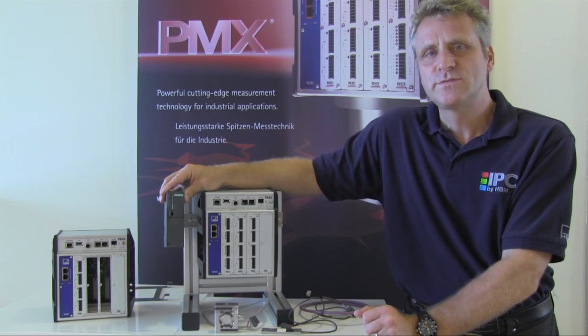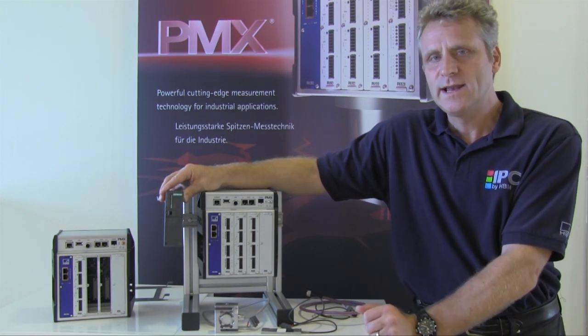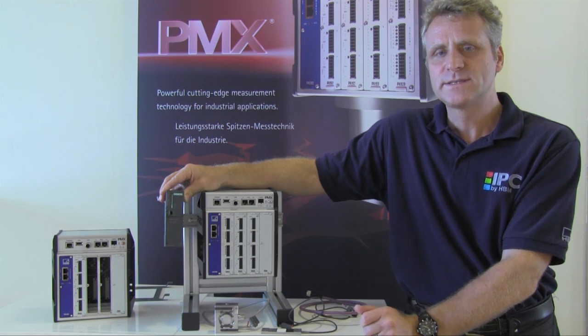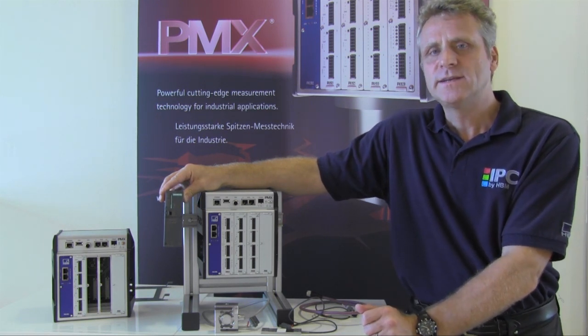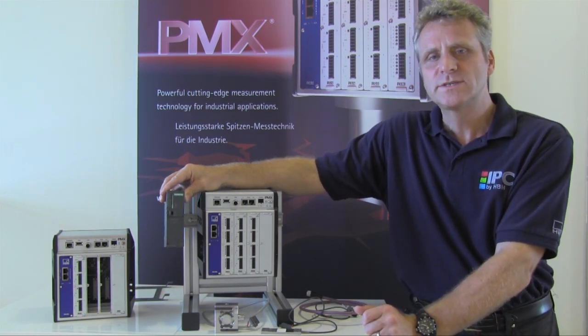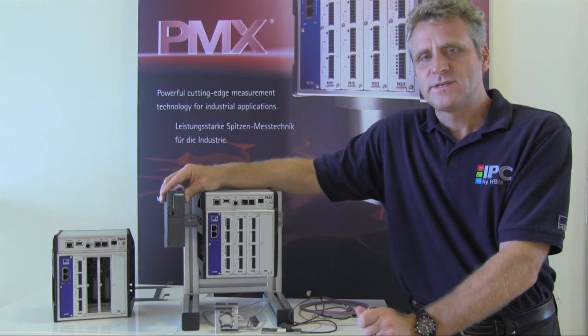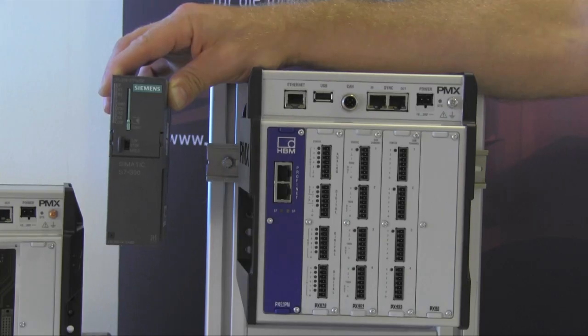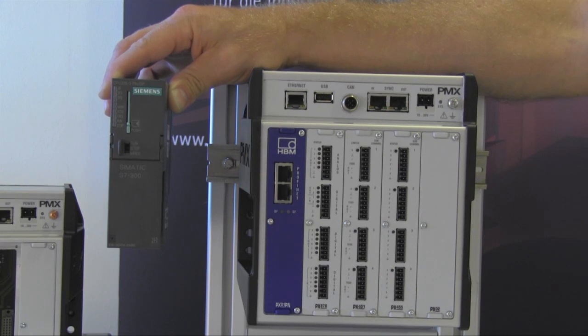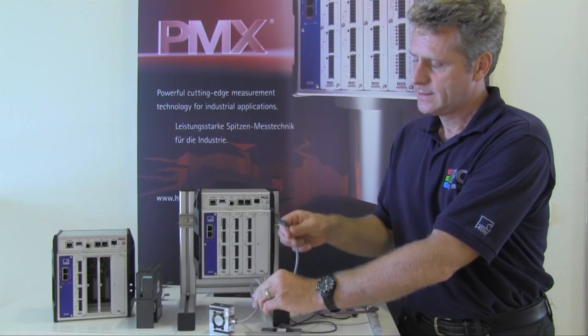Both field bus systems are designed to work as fast and efficiently as possible. This allows us to achieve high transmission rates. For EtherCAT, this means frame rates of up to 10 kHz, and for Profinet IRT operation at up to 1 kHz. Now we come to commissioning the PMX amplifier system.